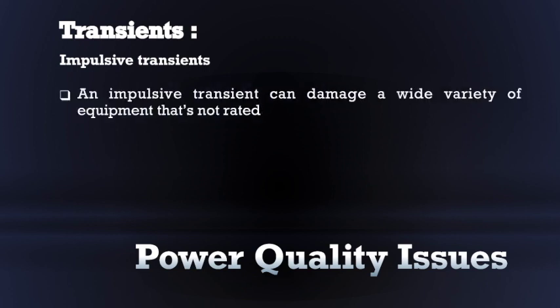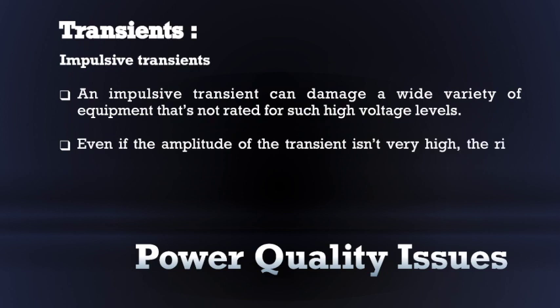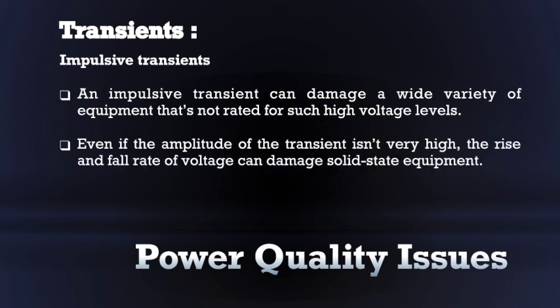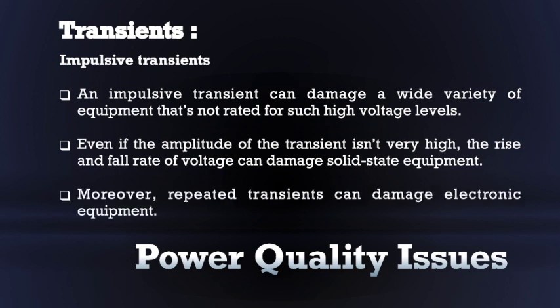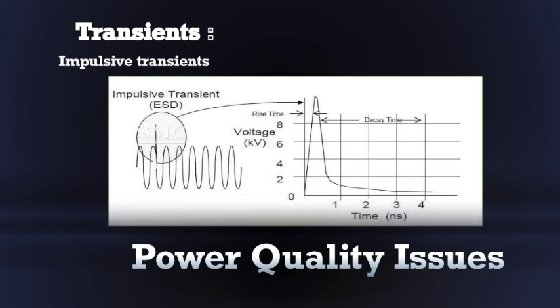An impulsive transient can damage a wide variety of equipment that is not rated for such high voltage levels. Even if the amplitude of the transient is not very high, the rise and fall rate of voltage can damage equipment. Moreover, repeated transients can damage it. Now you can see a figure. In this figure, an impulsive transient due to electrostatic discharge is shown. As you can see, it is unipolar in nature and the rise time of the waveform is in the range of less than 1 nanosecond.